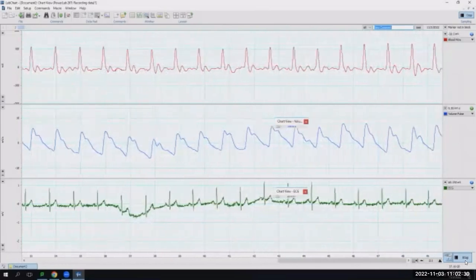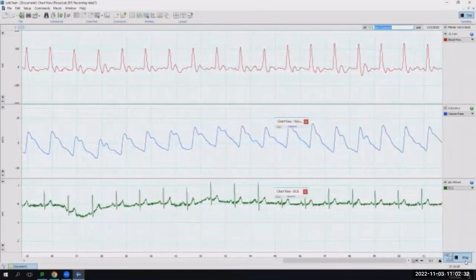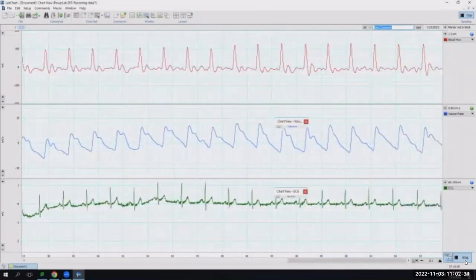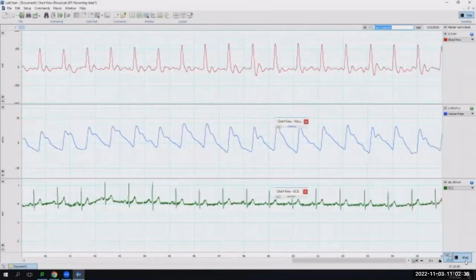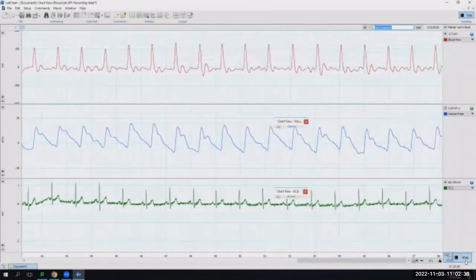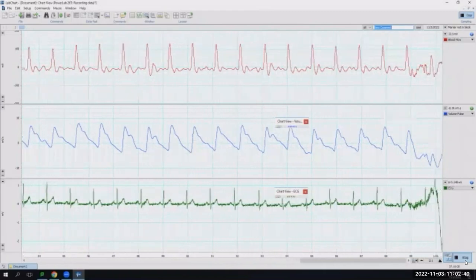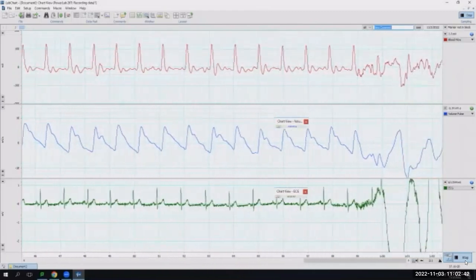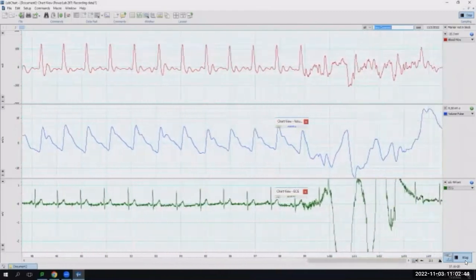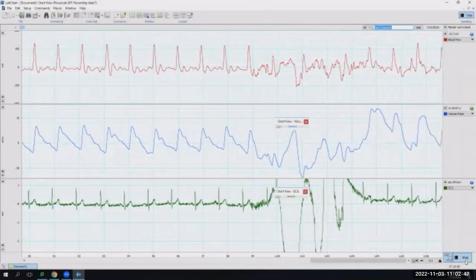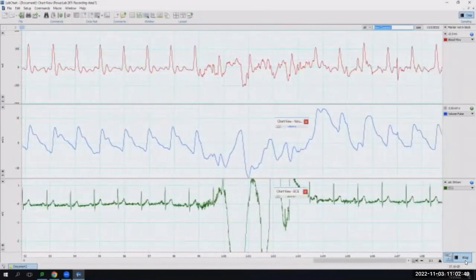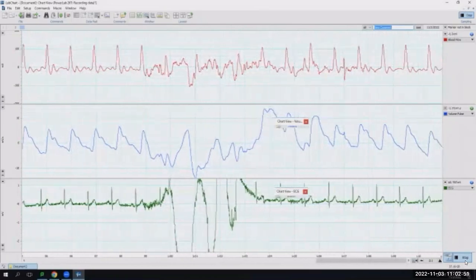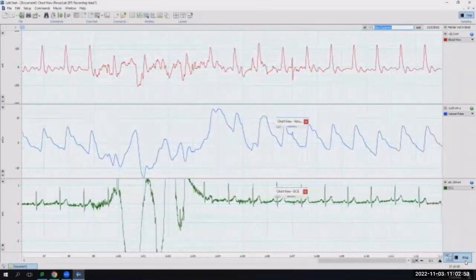Channel 3 is coming from our bioamp with our 3 leads. And this is the ECG. If we take a look at this, if we're not seeing an ECG, in this case, I've got an electrode that's lifting up right here. So reposition that, and as you can see, as I moved, I got a lot of static on the screen. And as I settle down, it looks a little bit better.